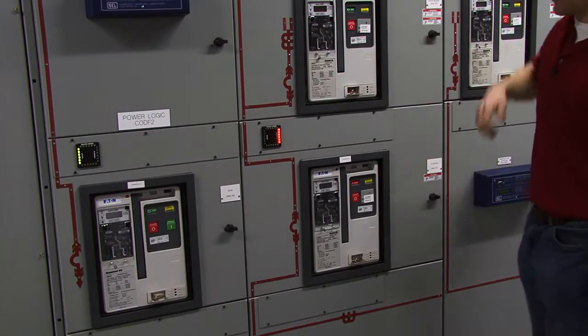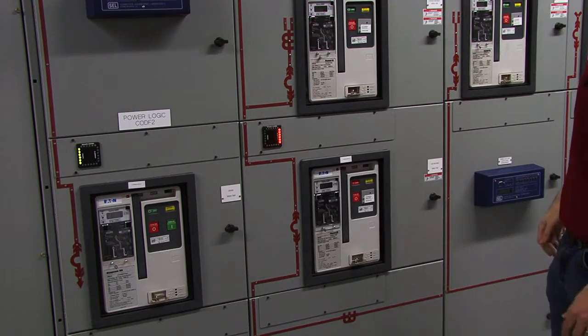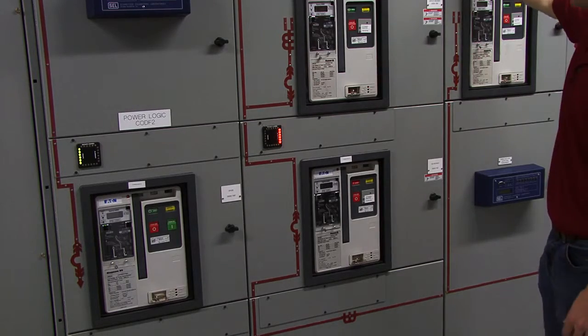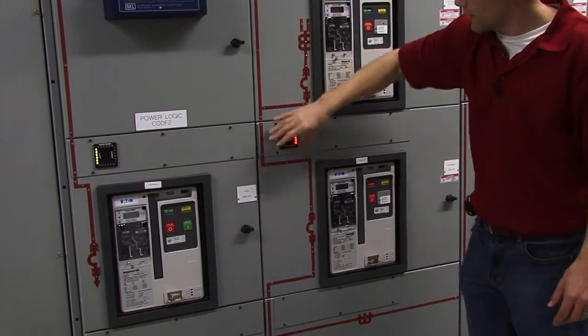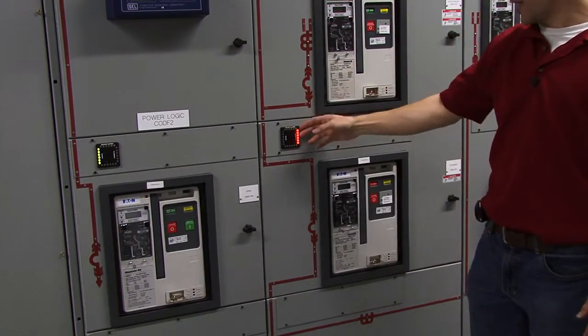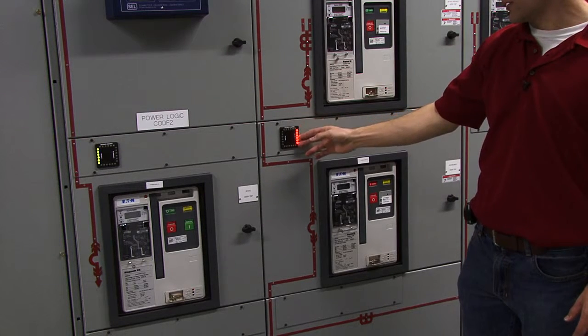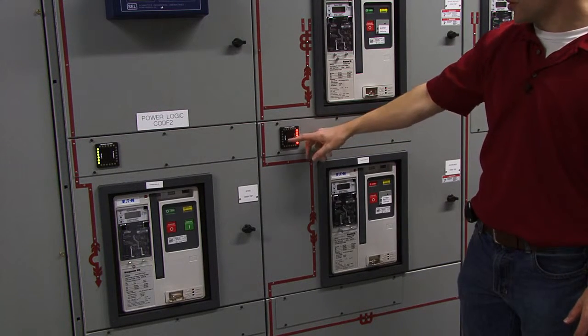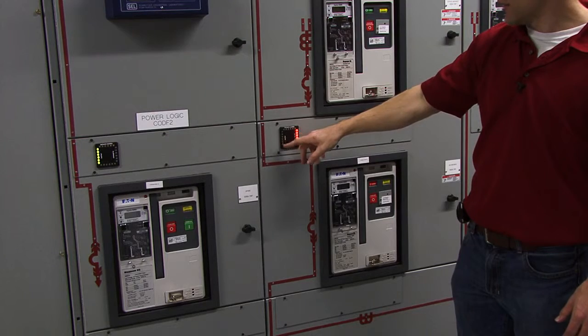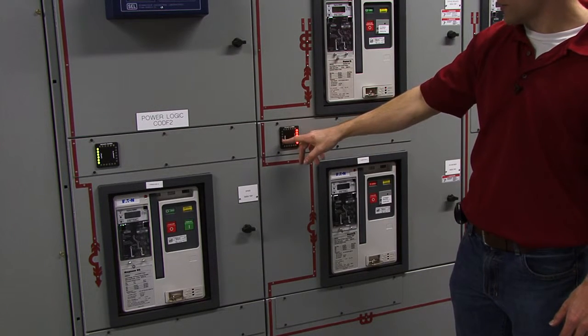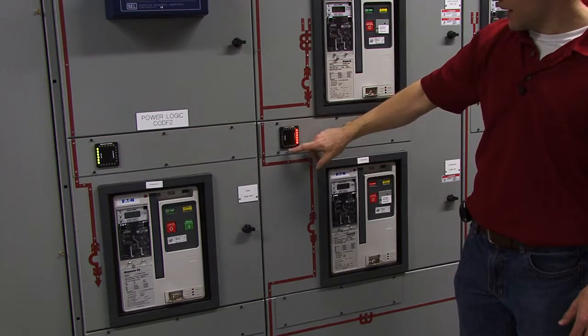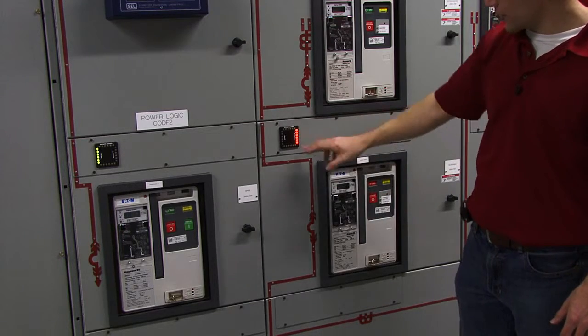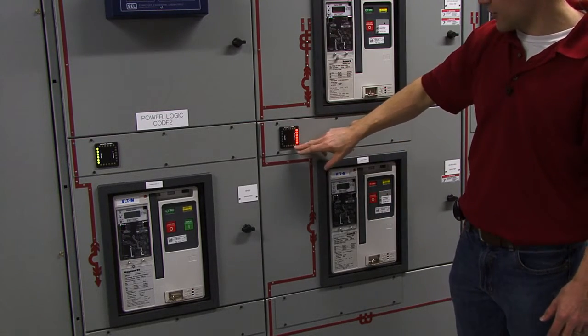And I didn't mention this, but it's true at the UPS input substations for the main and the maintenance bypass. There are LED blocks that show the status of the breaker. Red LEDs lit on the right-hand side is closed. Open LEDs on the left-hand side, which show up green, indicates the breaker is open. And if the breaker trips due to an overcurrent, it will blink yellow here and here.